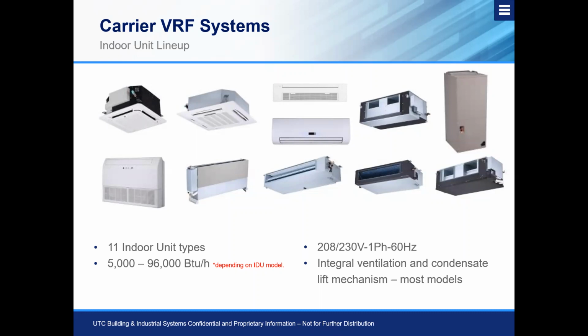So for example, the cassette style units have outside air knockouts that can have outside air ducted directly into that fan coil. However, that outside air does need to be pre-treated prior to sending that air into the unit because it cannot handle raw outside air. Those units also have built-in condensate lift mechanisms. And we put the emphasis on lift because it's just designed to lift the water out of the unit into a secondary pump or into a drainage system where that condensate can be drained out. It's always important to make sure that you reference the appropriate installation manual to know your maximum lift rating, as these do not have check valves built into them. And if that unit does shut its pump off after a cooling cycle and you are over the maximum lift rating, you certainly run the risk of overflowing the drain pan and causing a water leak situation in the space, which of course is never good.